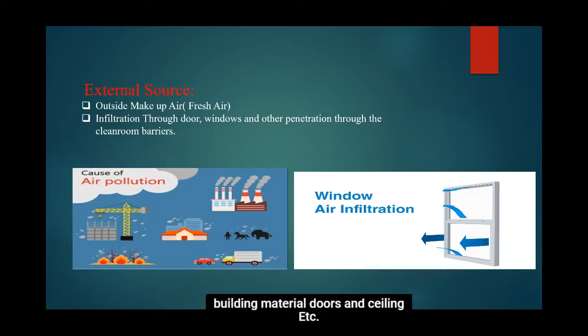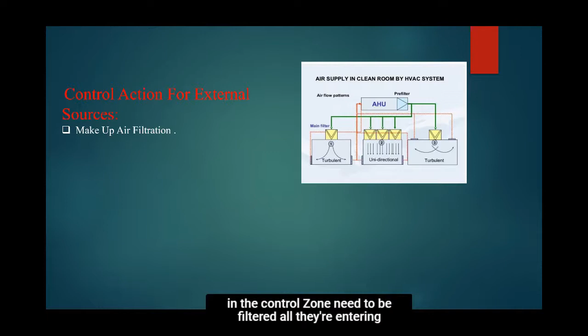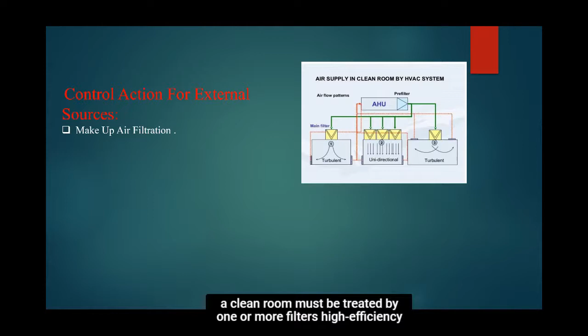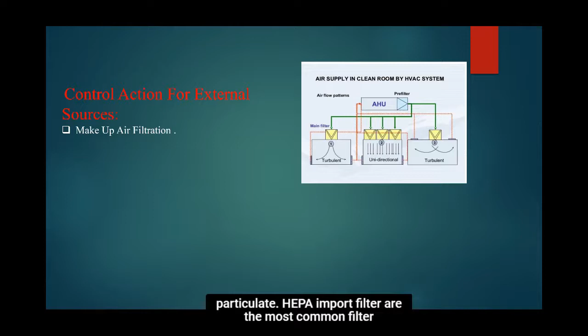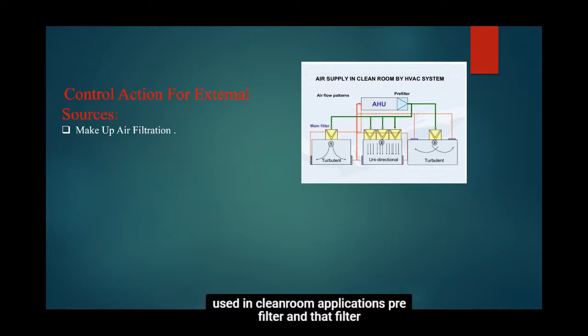First, we have to do makeup air filtration. In the AHU, we are taking 20% air as fresh air, and we should filter this fresh air. Any air introduced in the control zone needs to be filtered. All air entering a clean room must be treated by one or more filters. High efficiency particulate air, HEPA, or ULPA filters are the most common filters used in clean room applications. Pre-filters and bag filters are used before HEPA filters.